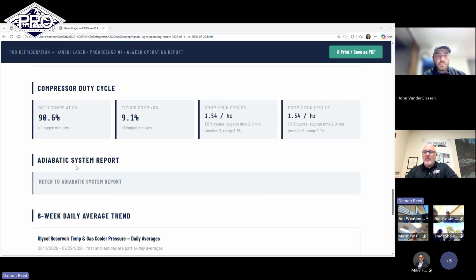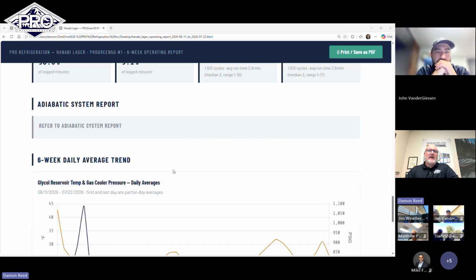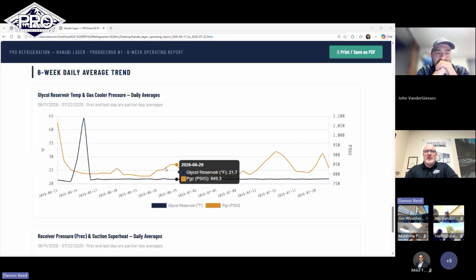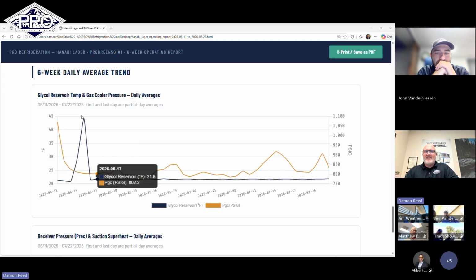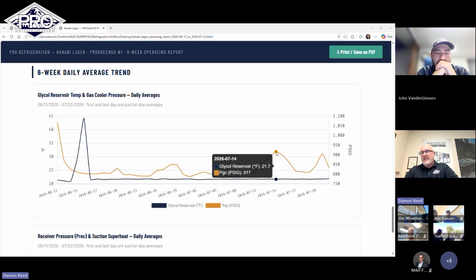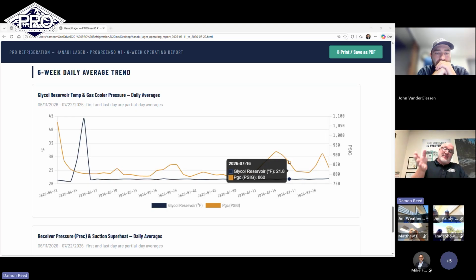The adiabatic system report, we'll talk about that separately because I've got some good information to share with you there. Then we did just a 6-week average trend over glycol reservoir temperature, gas cooler pressure. Again, we see these spikes, these anomalies. What happened? This yellow, where this peaks up, in the adiabatic report, I'll talk more about that. That's where we got some higher ambient temperatures, so I expect the gas cooler pressure to come up a little bit there.